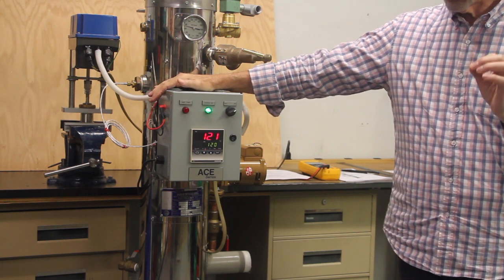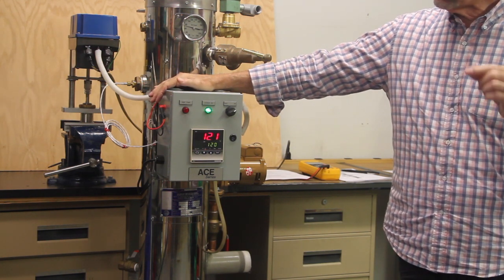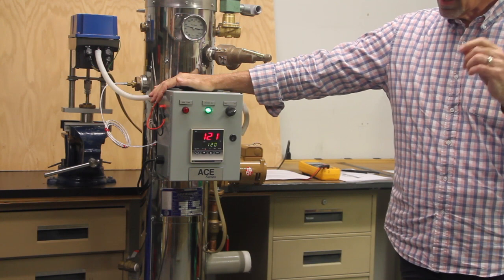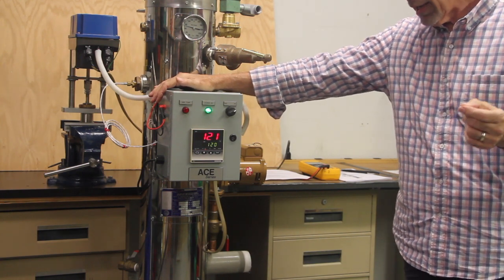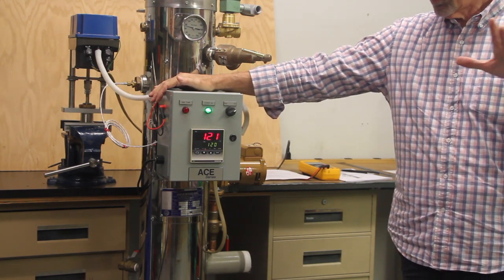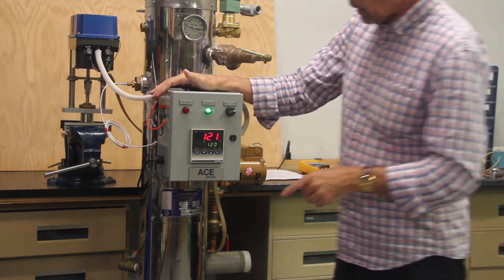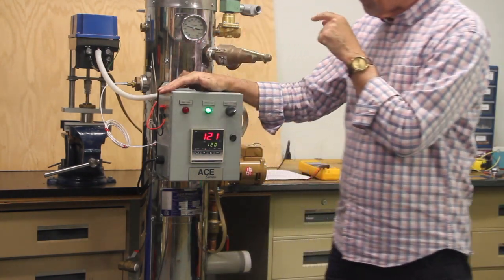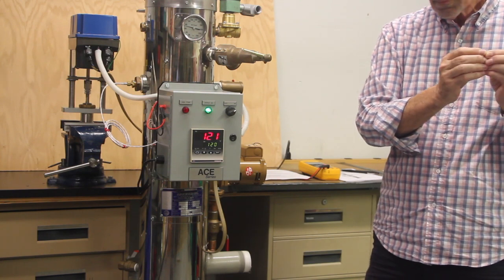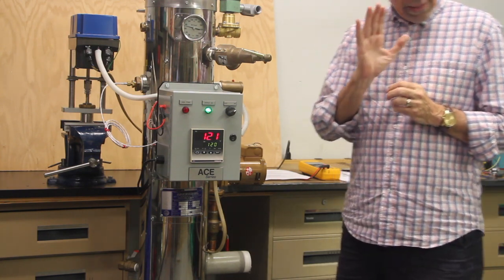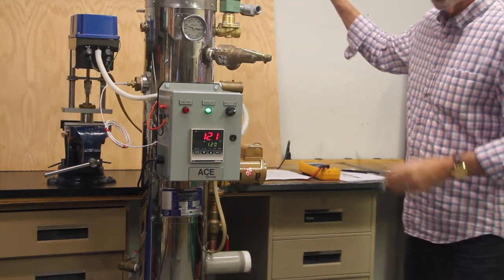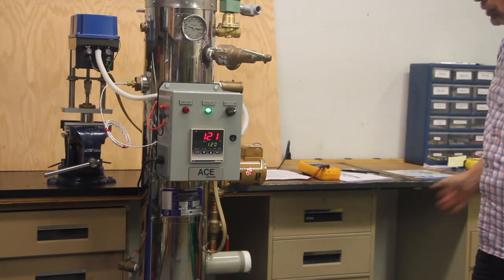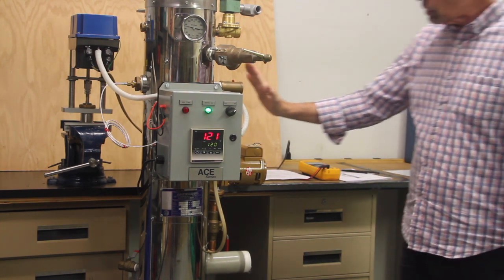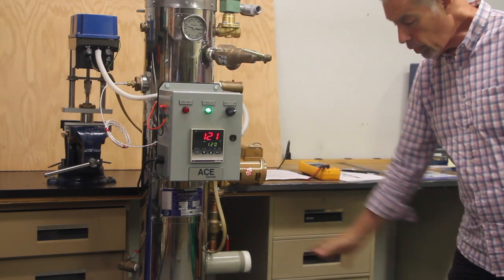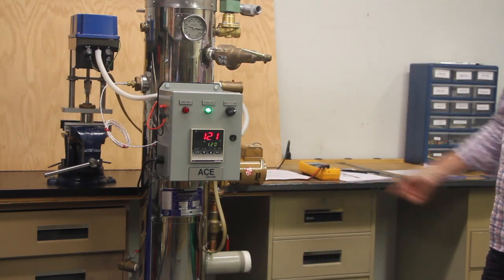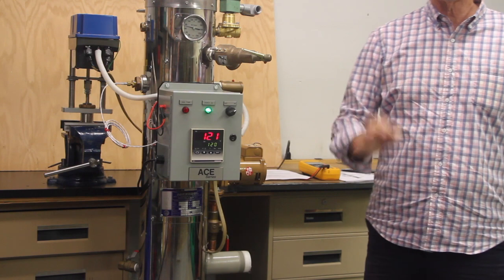Okay, we're going to talk about what happens if that control valve leaks by. They're not bubble tight shutoff. They're what they call class 4 shutoff. So on a weekend or a holiday, if there's nobody in the dormitory or nobody using any hot water, that valve will bleed by a little bit of steam. What we insist on is to have in your building recirculation system, which is outside of our scope, it plugs into the heater here or in the cold water line. You have a building recirculation pump, must be running all the time.